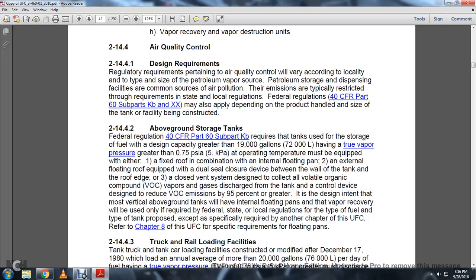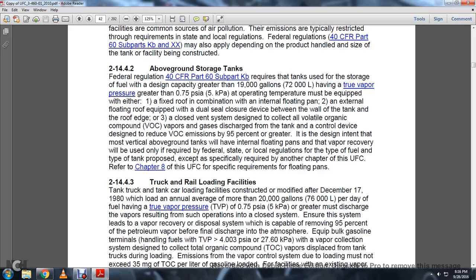If the design intent is met, most vertical aboveground tanks will have internal floating pans. Vapor recovery will be used only if required by federal, state, and local regulation for the type of fuel or tank proposed, and except if specifically required by another chapter of the UFC. Refer to Chapter 8 of the UFC, the Unified Facilities Criteria, for specific requirements for floating pans.